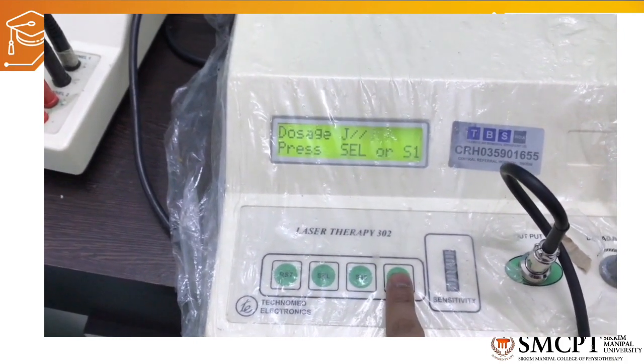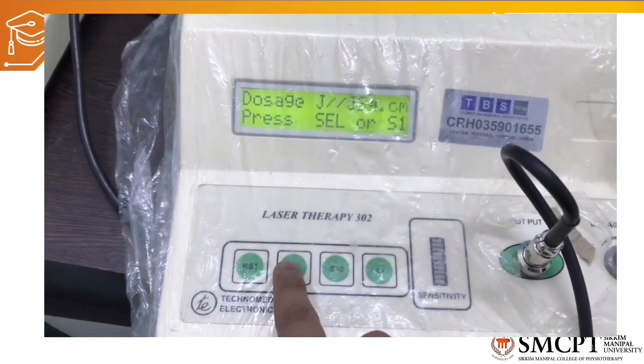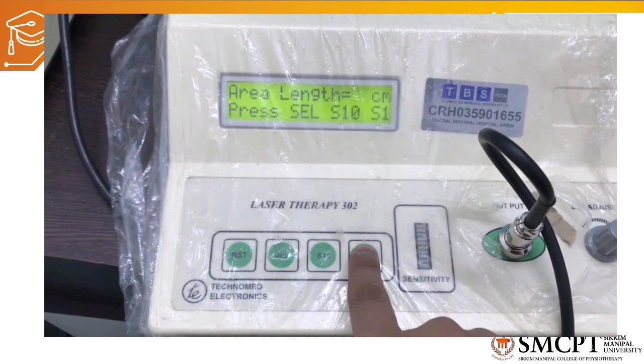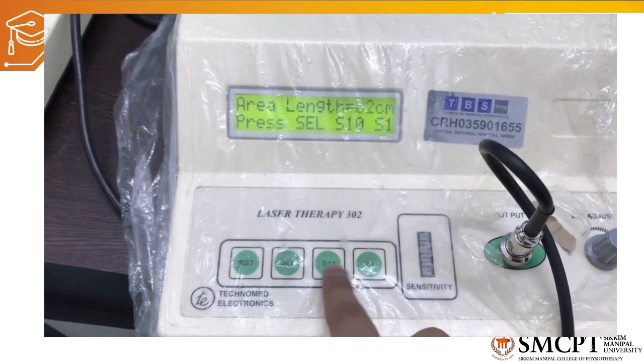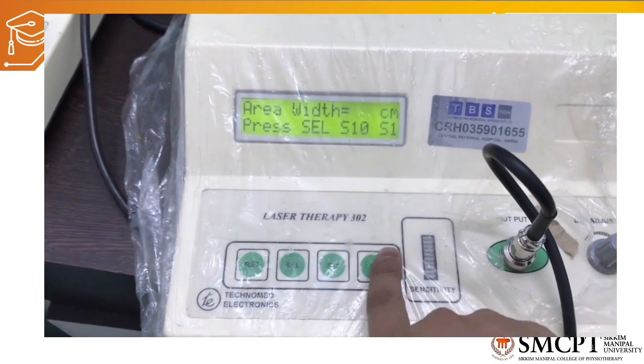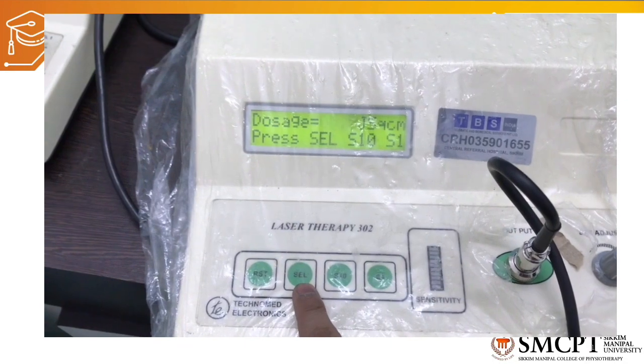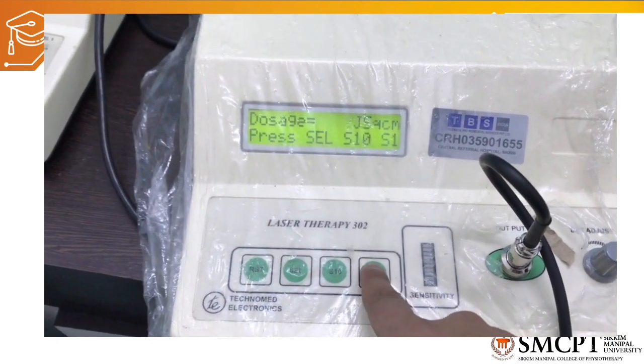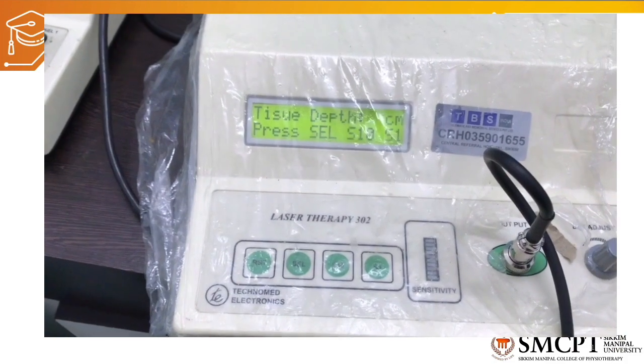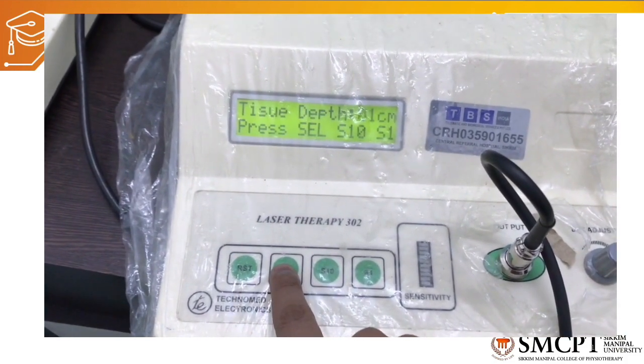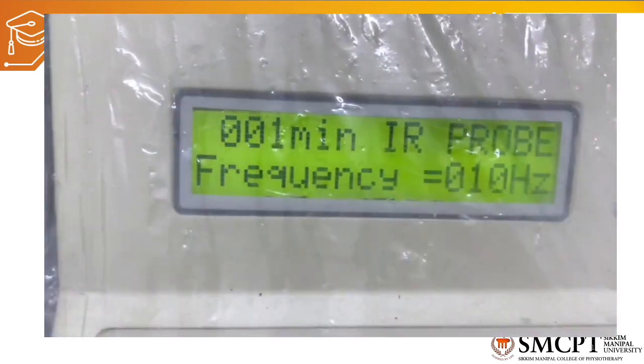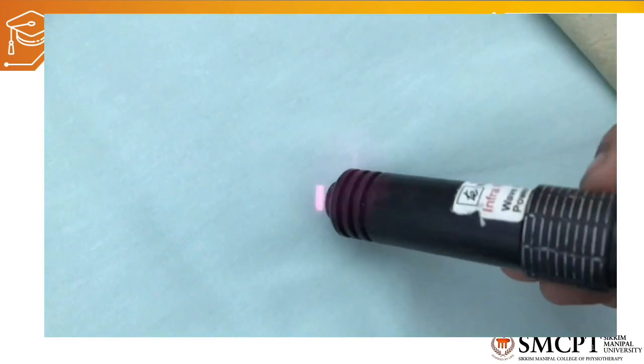The machine asks for intensity type — we select joules per centimeter square. We then enter the tissue length of 2 centimeters and width of 1 centimeter. For the dose, we enter 1.5 joules per centimeter square for wound healing, and a tissue depth of 1 centimeter. The machine automatically calculates the treatment time — in this case, 1 minute — using the pulse frequency selected.